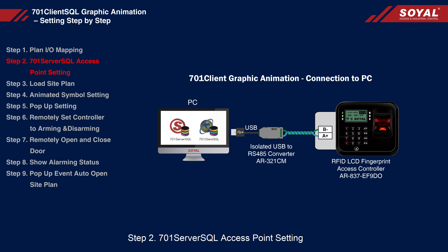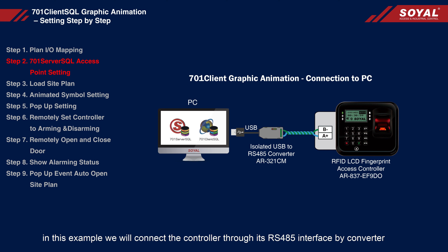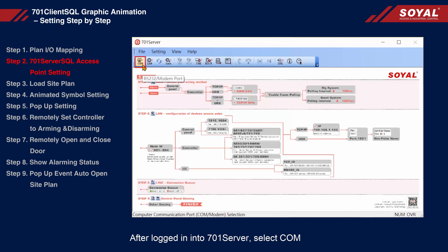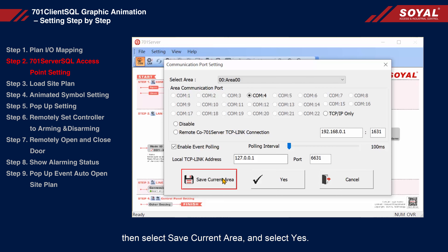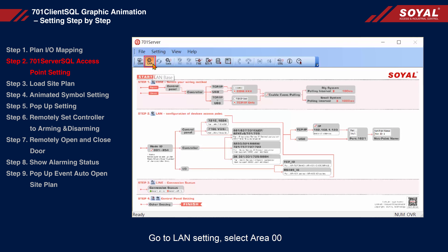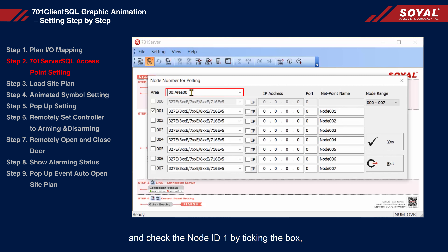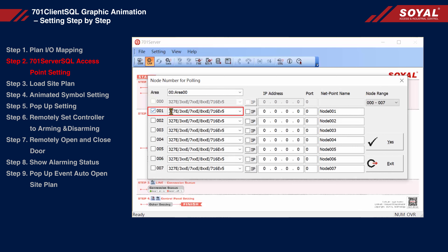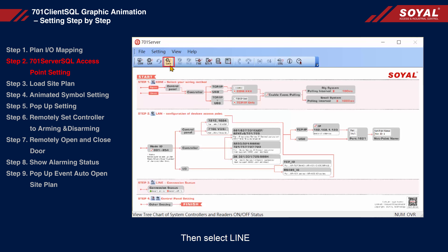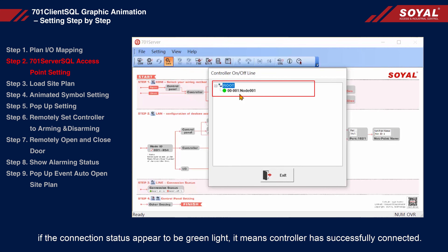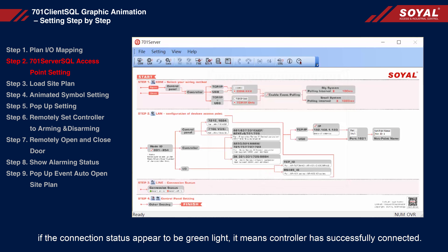Step 2: 701 server SQL access point setting. First, we will connect the controller to 701 server SQL. In this example, we will connect the controller through its RS-485 interface by converter. After logging into 701 server, select COM, select area 00, set area communication port to COM4, then select save current area and select yes. Go to LAN setting, select area 00, and check node ID 1 by clicking the box, select the correct model type, and select yes. Then select line. If the connection status appears as a green light, it means the controller has successfully connected.